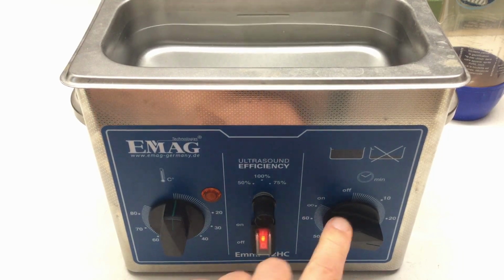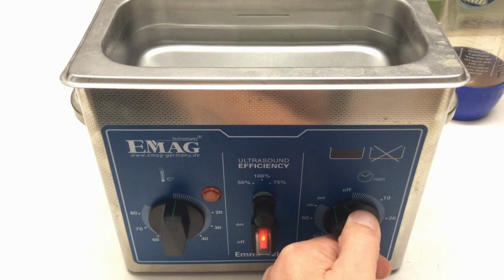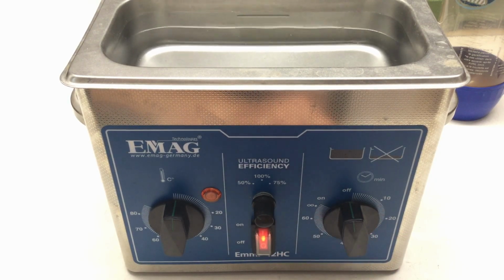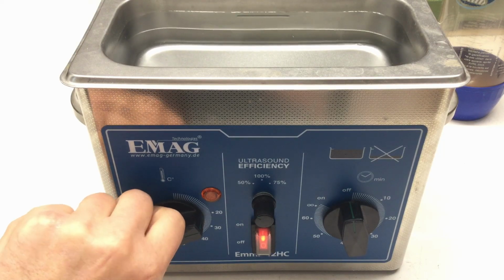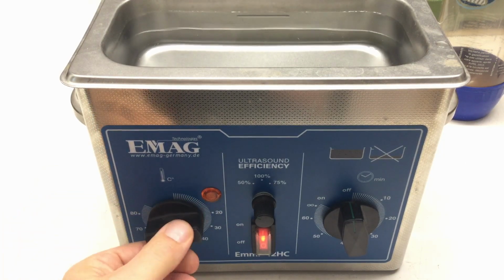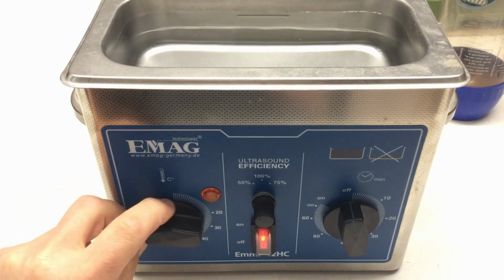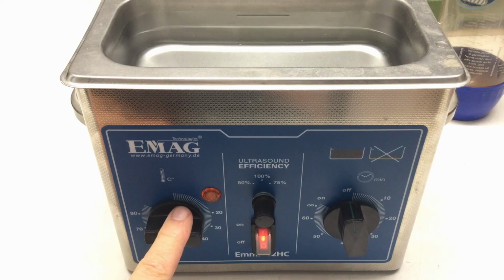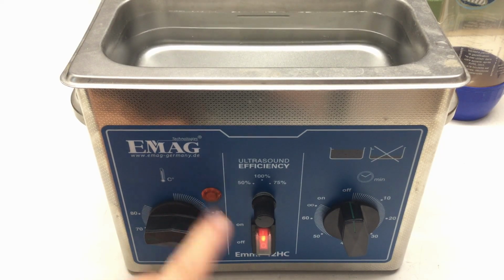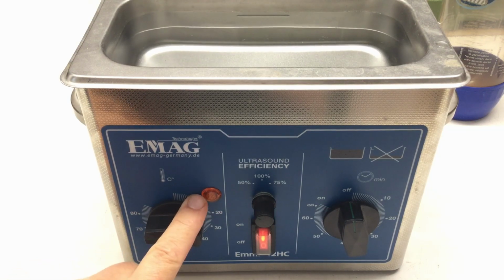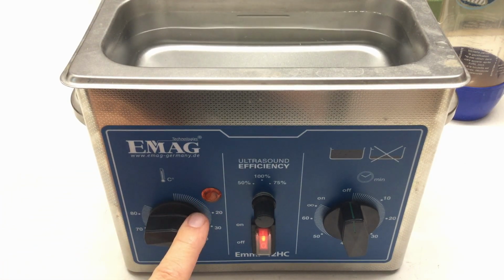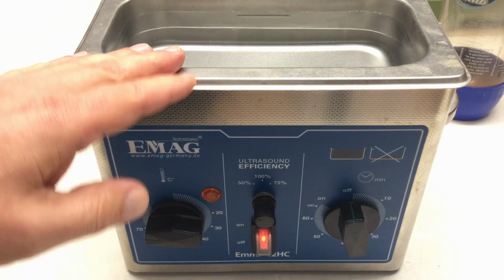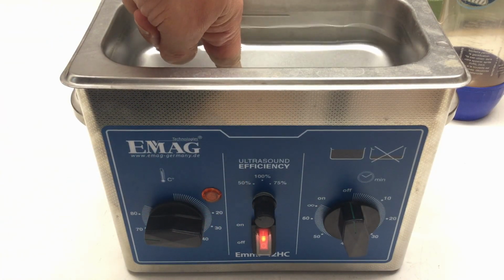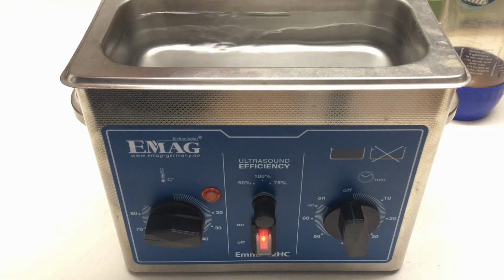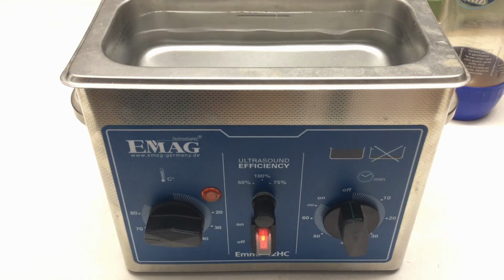No ultrasonic cleaning action, my finger is still dirty. So ultrasonic cleaning is out of the question - I hope this is not a mechanical failure. Let's see if we can switch on heating. Yeah, that light should come on when it heats, I guess, but it doesn't. Let's wait a while and then I'll tell you if the water got warmer, if it's just the light, or if there's a more serious issue. It's about 5 minutes later and the water is still not at 80 degrees, or it didn't heat up at all.